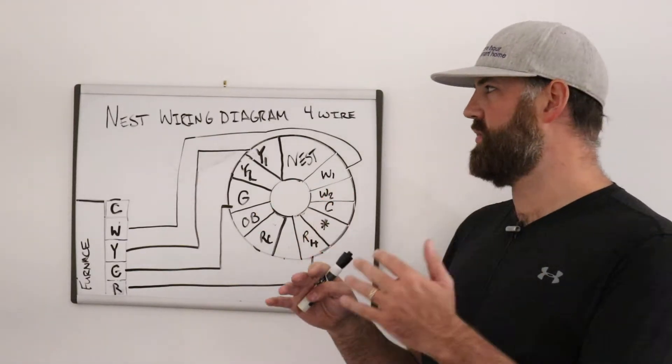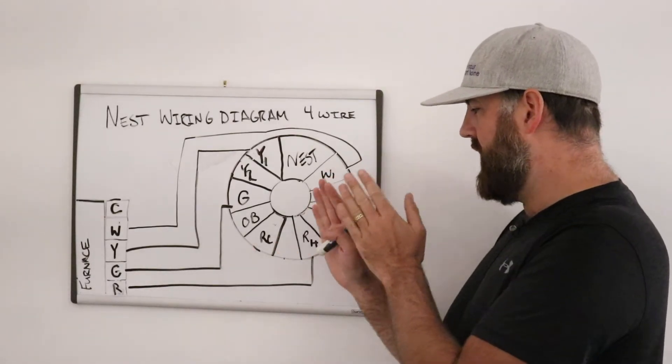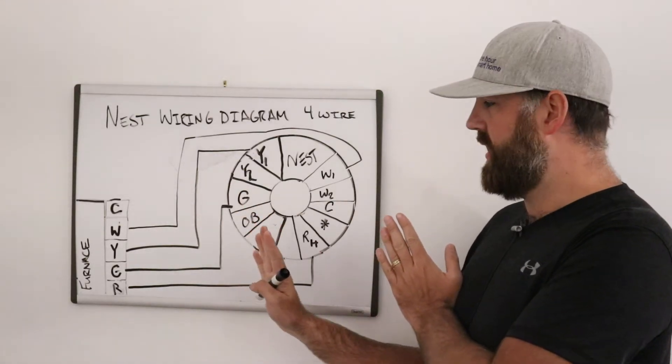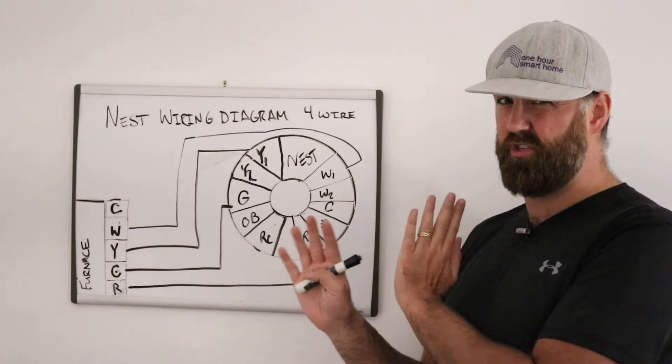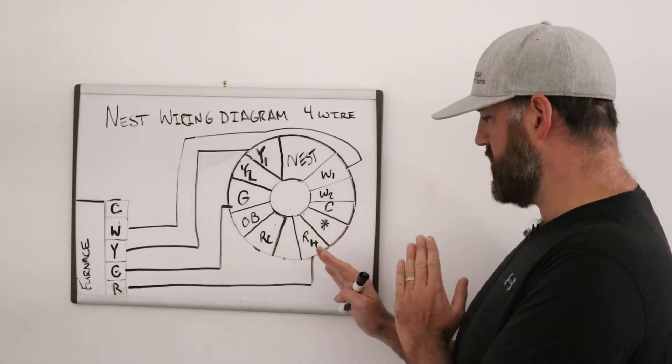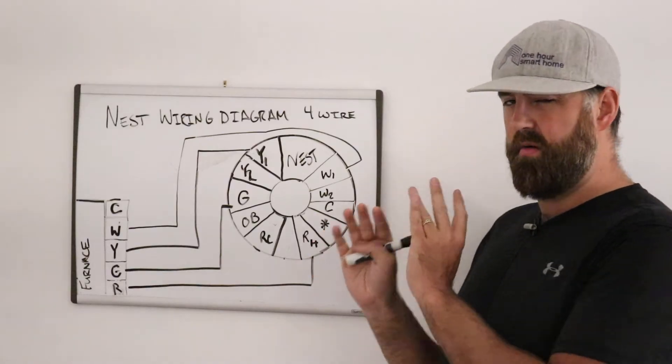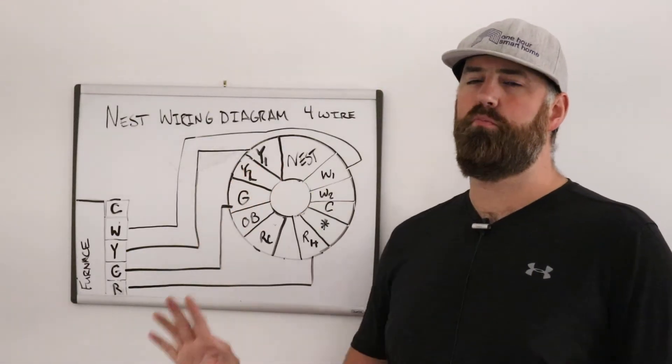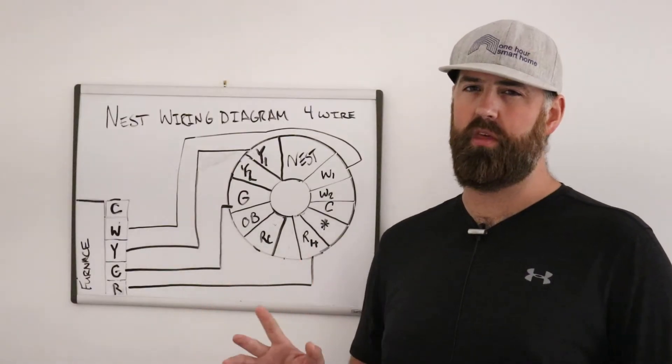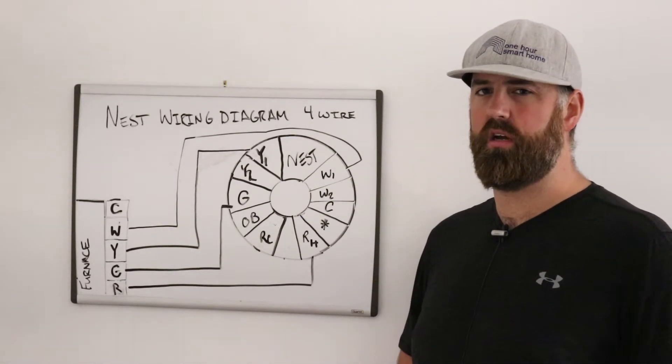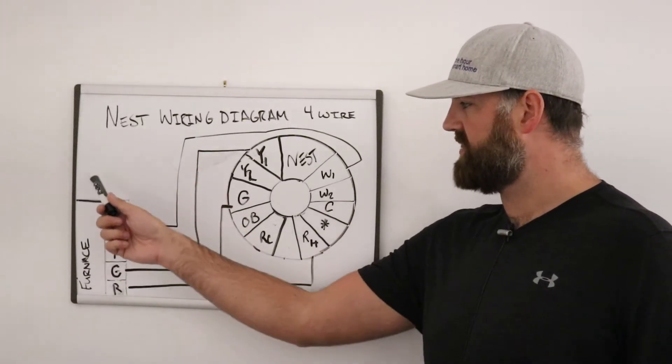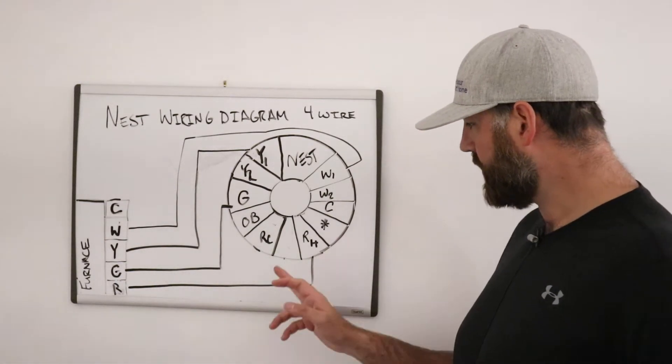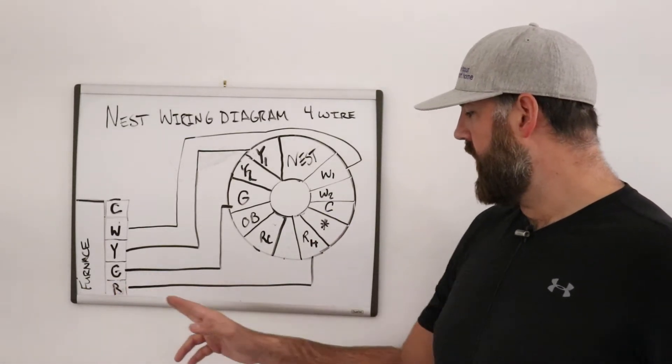So R, either RC or RH is just an input for power. That's what powers the nest. That is what goes through the nest and then provides a signal back down to the furnace. And it is designed in such a way that you could use RC for power from a separate cooling system, if it wasn't connected to your furnace and HVAC system, which is very rare, and you could have another power to your RH terminal from the heating system, which would be separate from your AC system. But these are both very rare occurrences. So RH is the power. We're going to have the R wire going from R to RH.